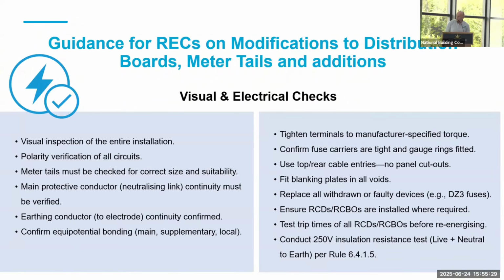The next one is the earth conductor to the electrode, continuity confirmed. This is another, I suppose, yeah, the industry would be crying out about this. So the earth conductor is the cable that leaves the distribution board and goes out to the earth rod, which is about 1.2 metres, and it's driven down into the ground. The registered contractors need to access and check this connection. So again, even in new installations or any alterations, the access to this electrode, or the earth spike as a lot of people would refer to it, needs to be accessible. Especially, again, going back to carrying out your periodic inspection report in time to come.